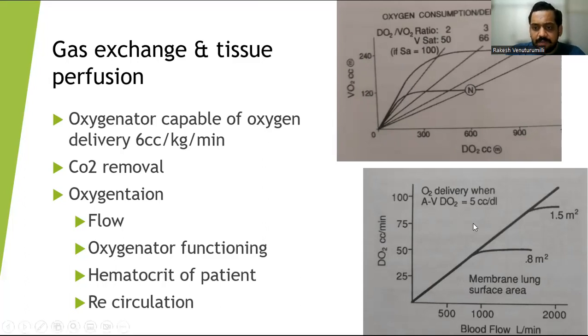Okay. Coming to the lower graph here, it's a graph plotted between your delivery of oxygen and the blood flow from the oxygenator. If you see here, with a 1.5 meter square oxygenator surface area and a flow of around 2 liters, you are delivering oxygen of only around 100 ml. So you need to increase the surface area and you need to increase the flow so that the oxygenator is capable of delivering a minimum of around 6 ml per kg per minute, right? That is our target here, and that's the target of oxygenation. Coming to hematocrit, you need to maintain a minimum hematocrit of around 40. Try to decrease the recirculation. The maximum acceptable recirculation on any VV ECMO should be around 30%.